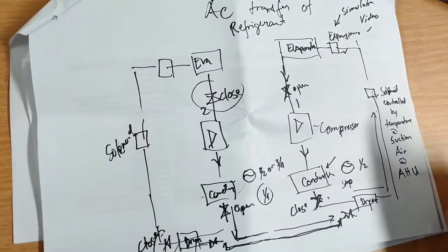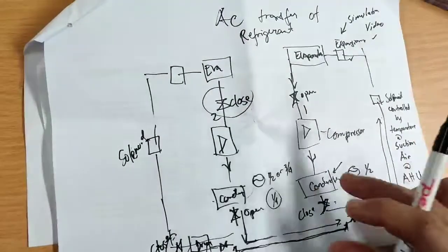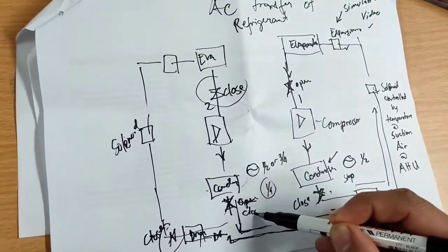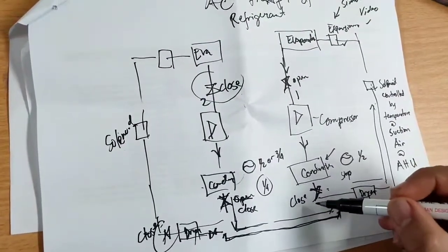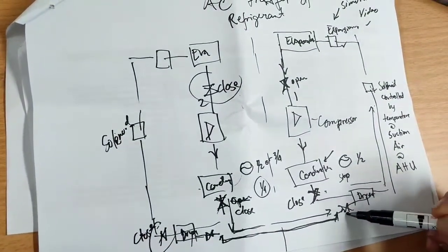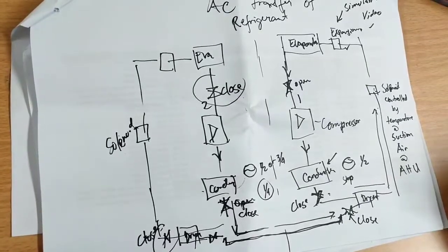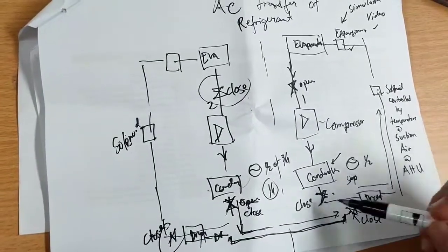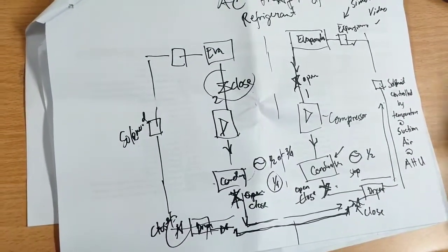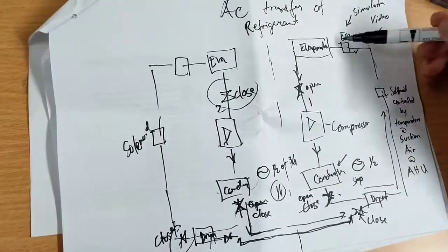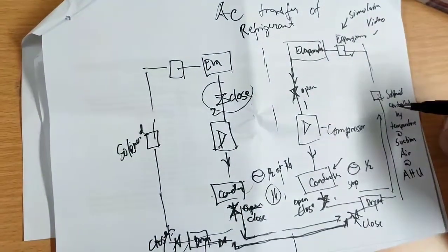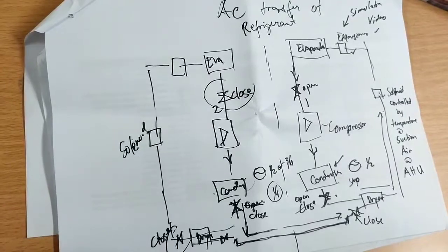just stop the compressor number 1, or close this one. Close number 1 after condenser, and then let low suction trigger. After low suction is triggered, the compressor automatically stops. Then open this after condenser for normal operation. Okay, that's it. I hope I explained or answered your question.